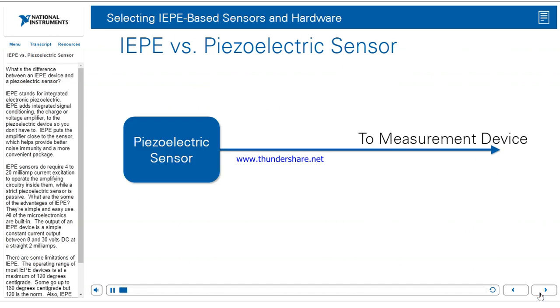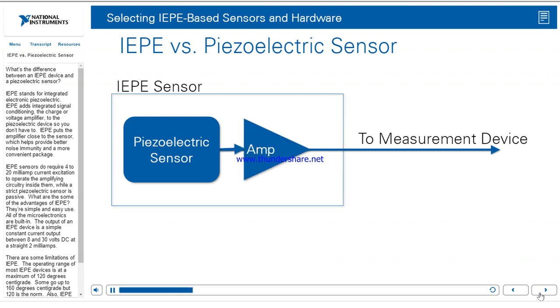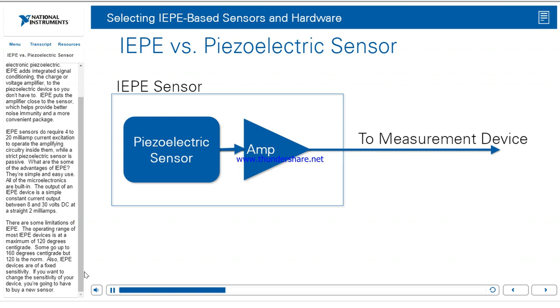What's the difference between an IEPE device and a piezoelectric sensor? IEPE stands for Integrated Electronic Piezoelectric. IEPE adds integrated signal conditioning — the charge-to-voltage amplifier — to the piezoelectric device so you don't have to. IEPE puts the amplifier close to the sensor, which helps provide better noise immunity and a more convenient package. IEPE sensors do require 4 to 20 milliamp current excitation to operate the amplifying circuitry inside them, while a strict piezoelectric sensor is passive.